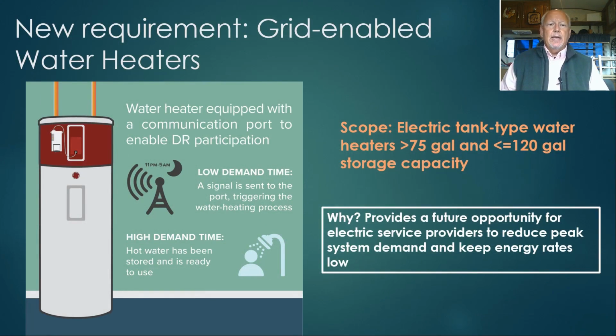Another change that's been made to the performance of water heaters is for new electric tank type water heaters greater than 75 gallons but less than 120 gallons in storage capacity. If you specify or plan to install an electric water heater that meets this criteria, that water heater needs to be grid enabled. So what is grid enabled? Grid enabled is a water heater that's equipped with a communication port to enable demand response participation.